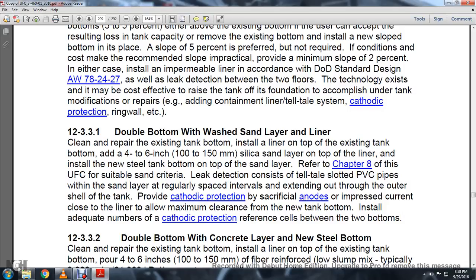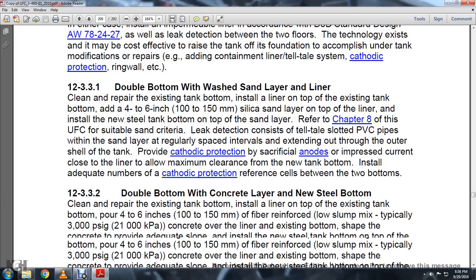Section 12-3-3-1: Double bottom with sand layer and liner. Clean and repair the existing tank bottom and install a liner on top. Add a four- to six-inch silica sand layer on top of the liner, then install the new steel tank bottom on top of the sand layer. Use suitable sand criteria consistent with the UFC. For leak detection, use telltale PVC pipes spaced at regular intervals extending through the outer shell of the tank. Provide cathodic protection with sacrificial anodes and impressed current. Install an adequate number of cathodic protection reference cells between the two bottoms.